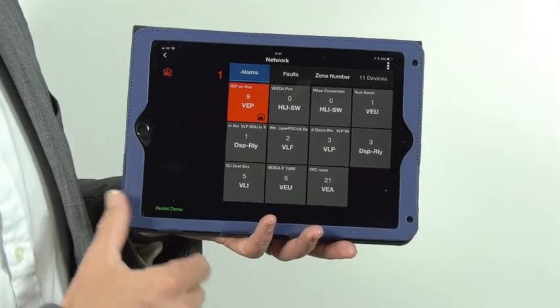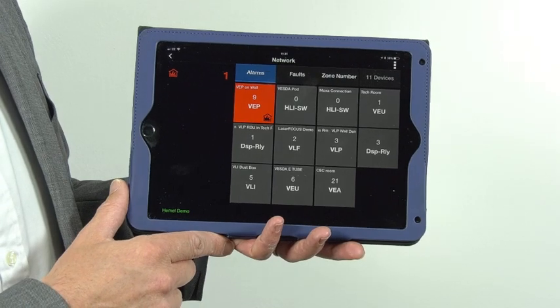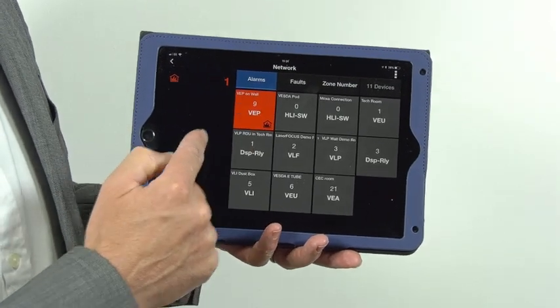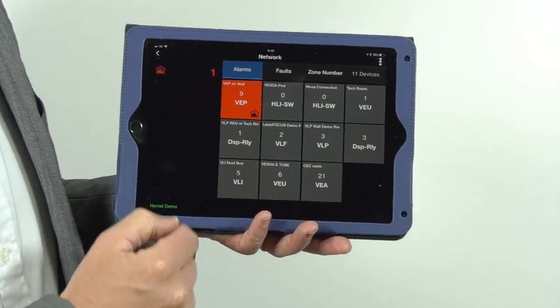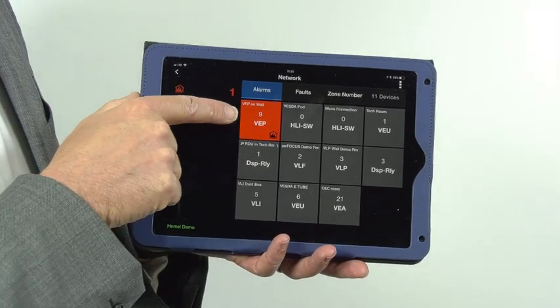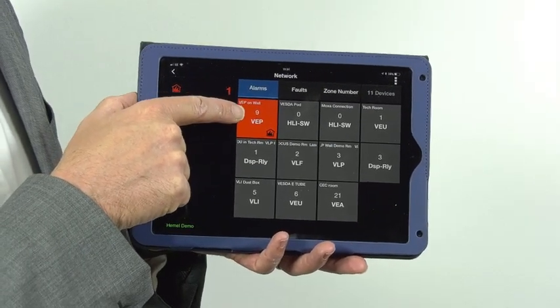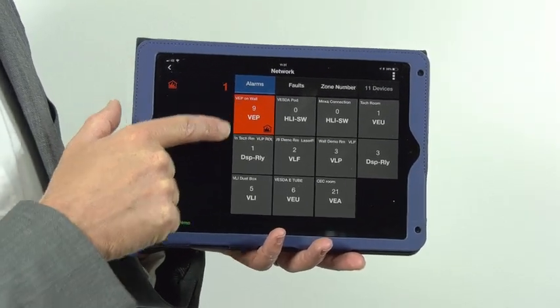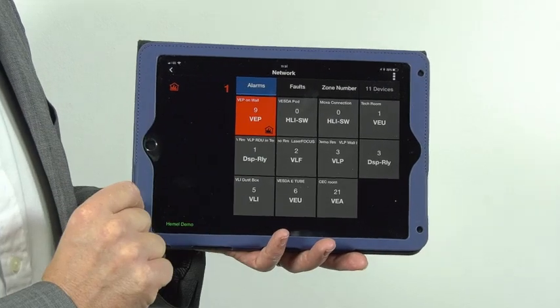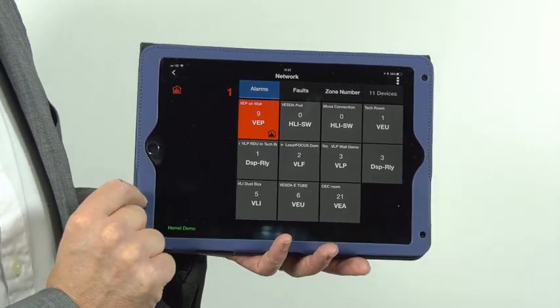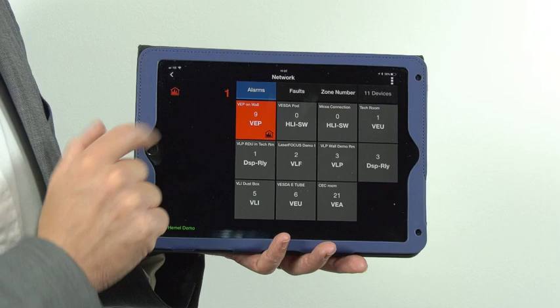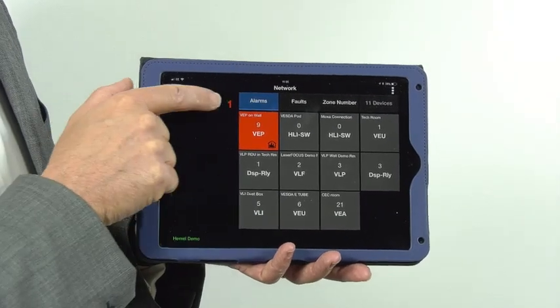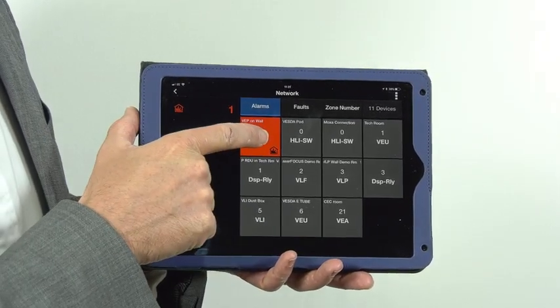This is a connection to a live network showing a number of devices. We have a VEP detector, a laser focus, and a laser plus detector on this network. The VEP has an alarm—we can see we've got a fire alarm with one alarm raised, and the VEP is the one in alarm.